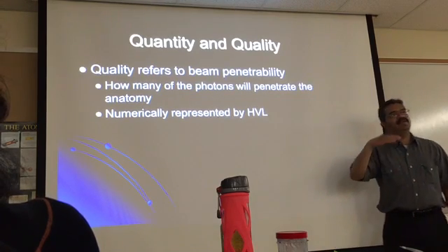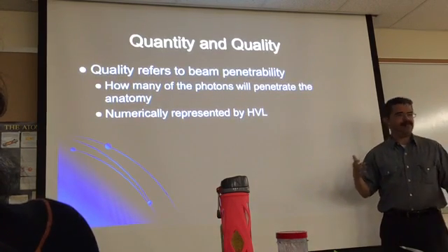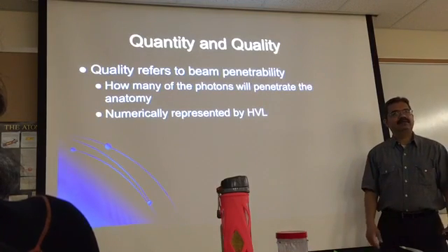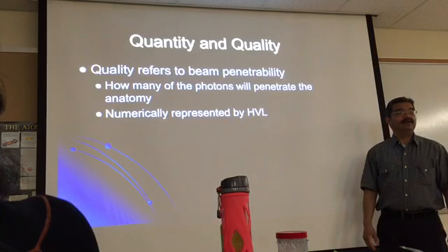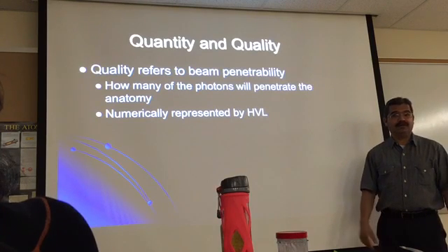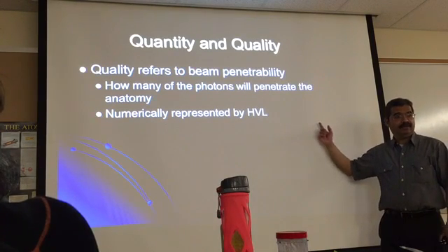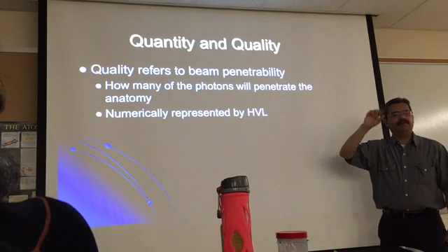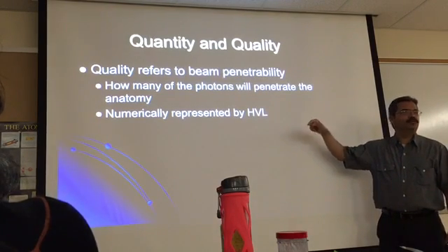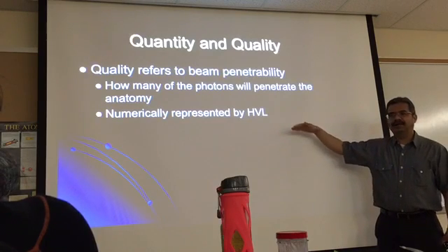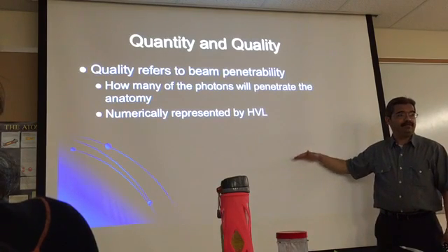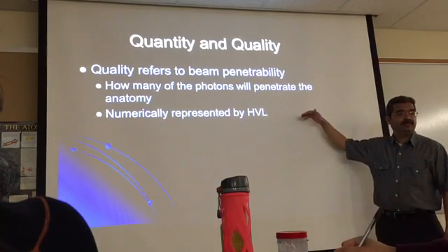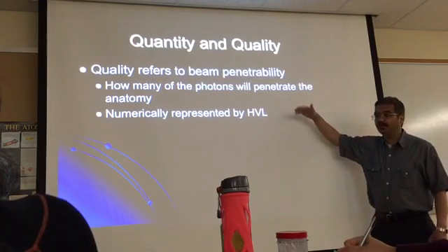Now, kVp set at 80, which is typically where you measure it. But how about if we go to 120? 3.2 is not going to do it. You're going to need more. 3.2 is the standard. Typically at 80 kVp, 3.2 is what will cut your intensity by half. But if you're using 100 or 120, it will be more.